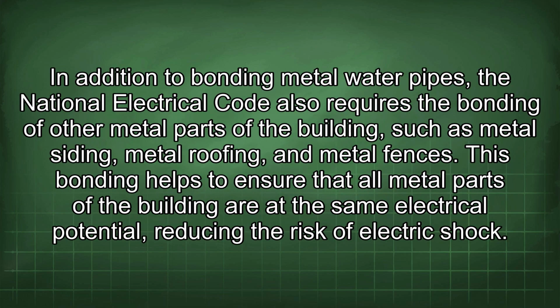In addition to bonding metal water pipes, the National Electrical Code also requires the bonding of other metal parts of the building, such as metal siding, metal roofing, and metal fences. This bonding helps to ensure that all metal parts of the building are at the same electrical potential, reducing the risk of electric shock.